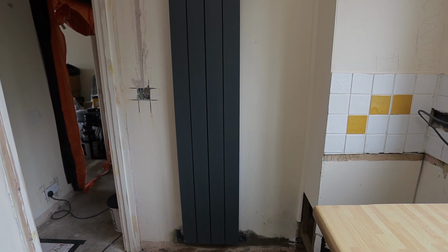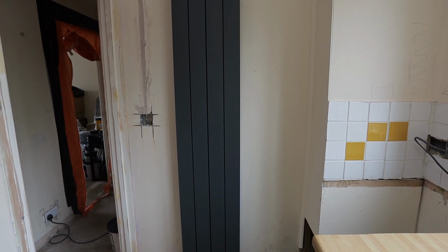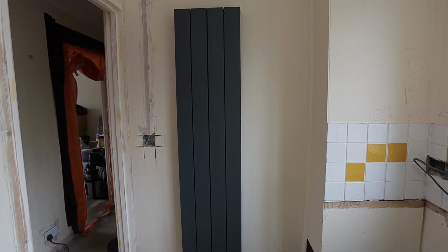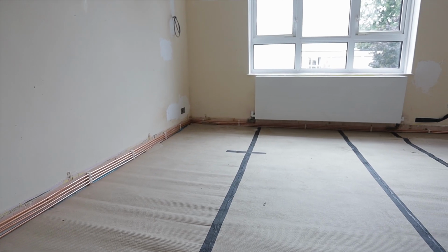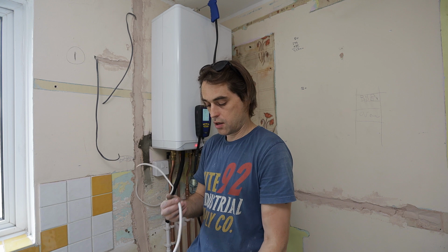Now, I've got my radiators installed on microbore throughout the property, apart from the bathroom radiator that will be installed when the bathroom is finished. I'll have to wait for the kitchen fitters to install the kitchen, then I'll come back and put a water softener in place. And also I have to wait for the electrician, and right now I'm running on just a plug, so I can commission the boiler.